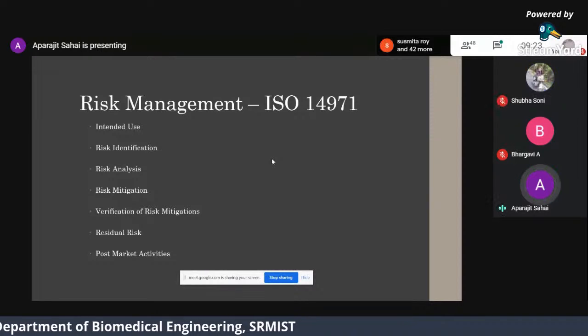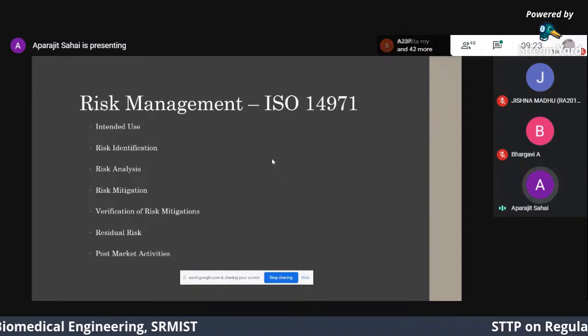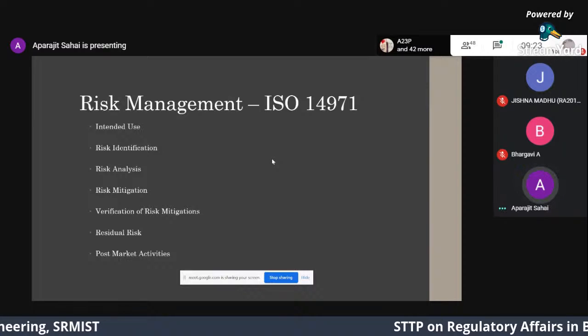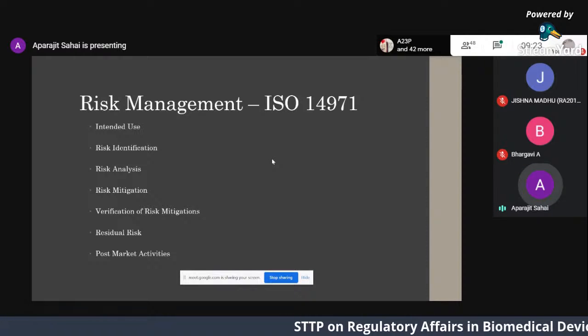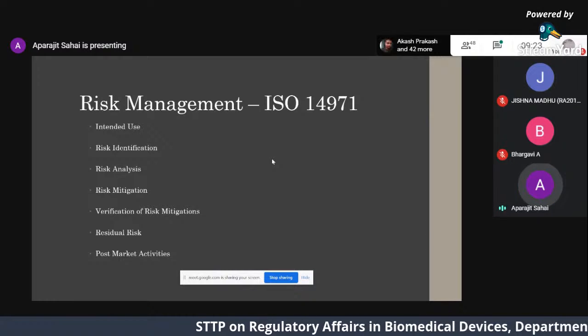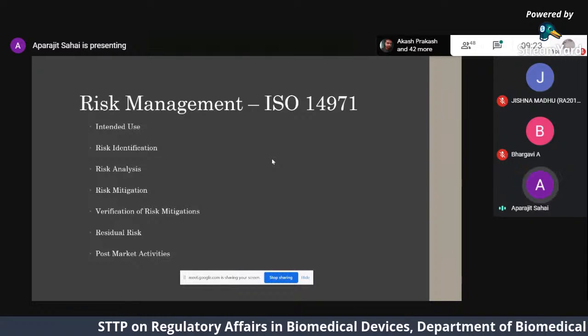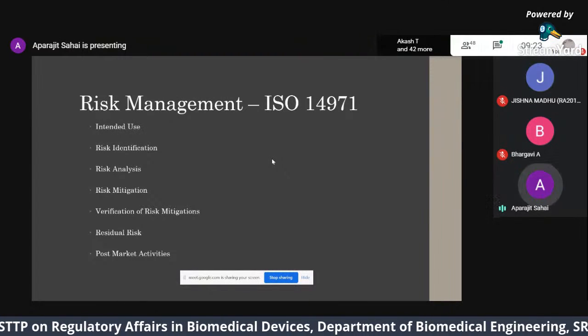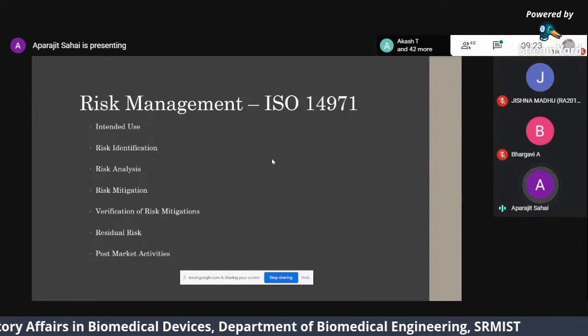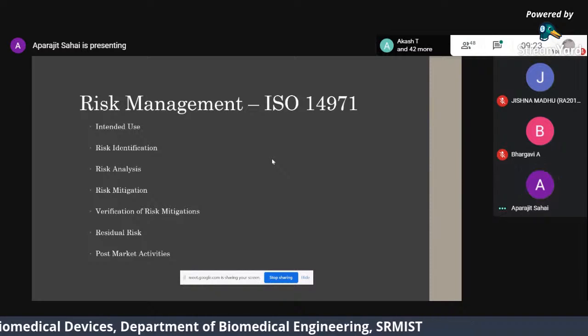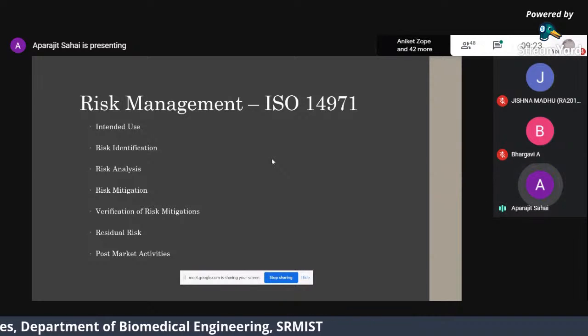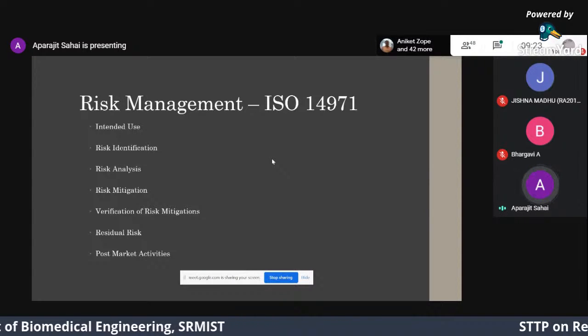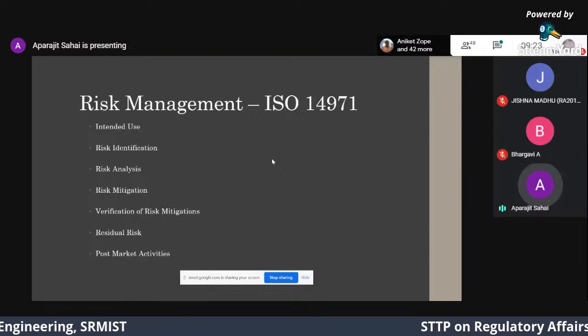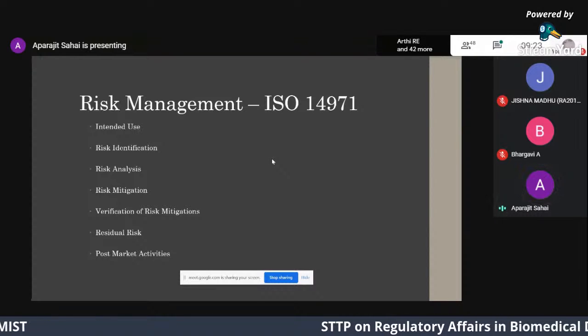Then it comes to risk identification, identifying specific risks. Is this device going to shock the patient? Is it going to shock the operator? Is it going to fall on someone and kill someone? So specific risk identification. Then risk analysis is about determining the probability and severity of harm. So if you've identified a risk, how severe is the harm that comes from that risk, and how probable is it?